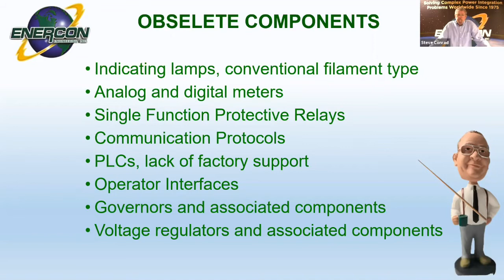The benefits of current technology: you're definitely going to have improved reliability. If you have component failures, at least you'll be able to get replacements because it's current. Increased and integrated functionality, as I mentioned, protective relays and similar devices are all integrated into multi-function devices now, meaning fewer components required, less wiring, fewer connections, and fewer points of failure, which increases reliability.